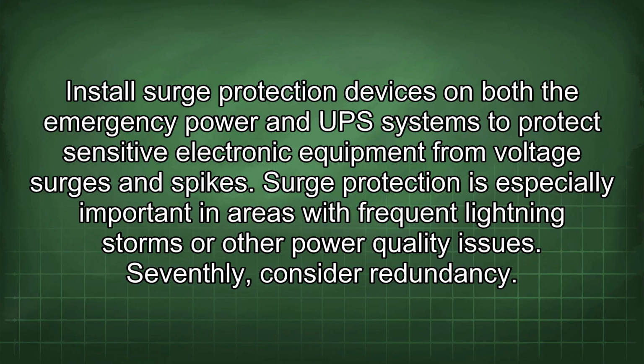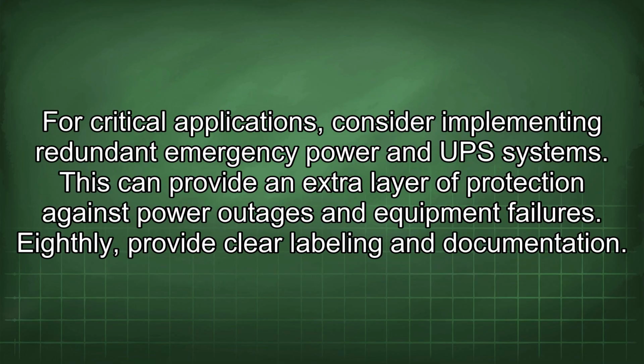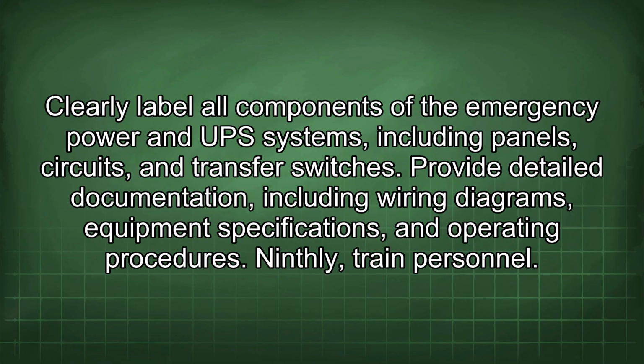Seventhly, consider redundancy. For critical applications, consider implementing redundant emergency power and UPS systems. This can provide an extra layer of protection against power outages and equipment failures. Eighthly, provide clear labeling and documentation. Clearly label all components of the emergency power and UPS systems, including panels, circuits, and transfer switches. Provide detailed documentation, including wiring diagrams, equipment specifications, and operating procedures.